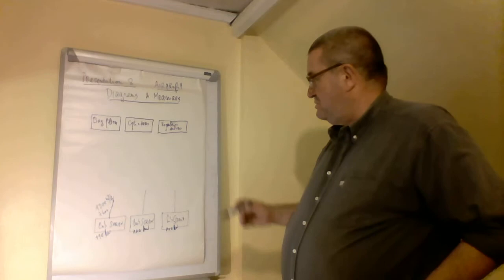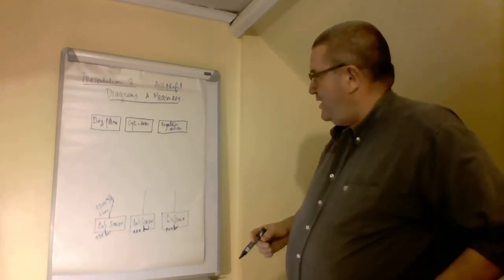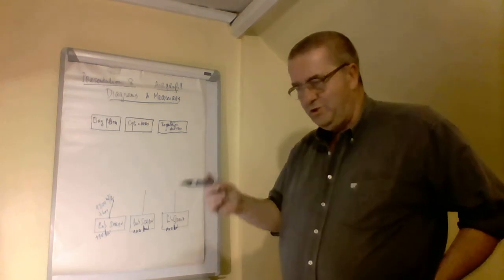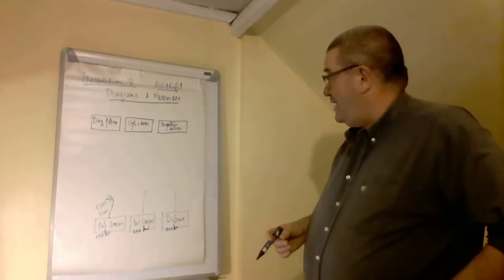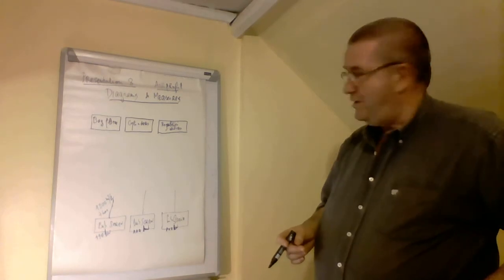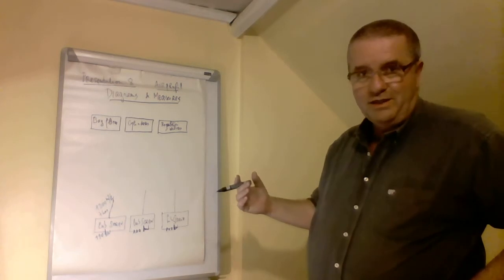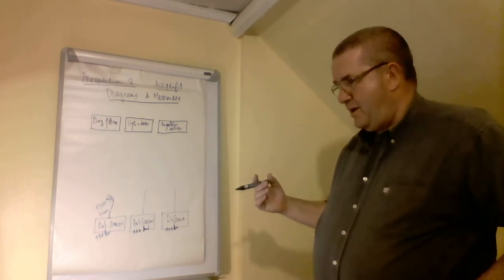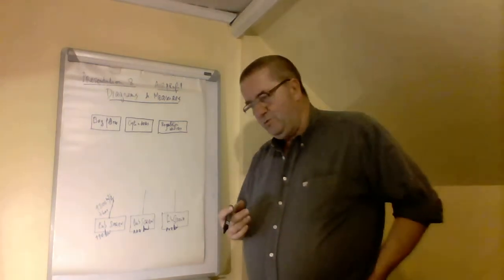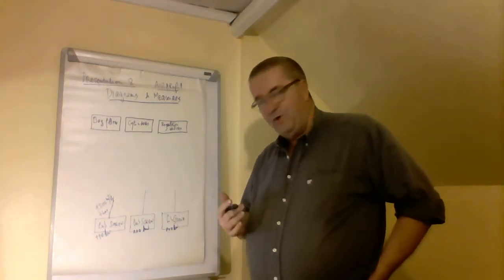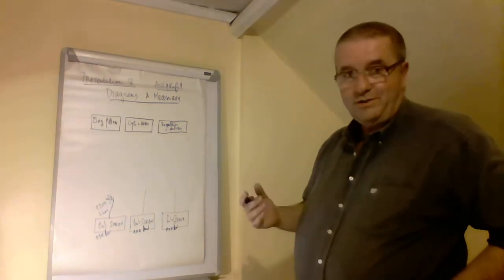So he wants the best reasonable treatment for air, because he knows that there should be no dust, no water, no liquid water, certainly no ice, and no oil, not too much oil, because some analog regulation devices will be blocked, or will suffer, or will make wrong measurements and wrong regulation if you have liquid water or oil or dust inside the air.